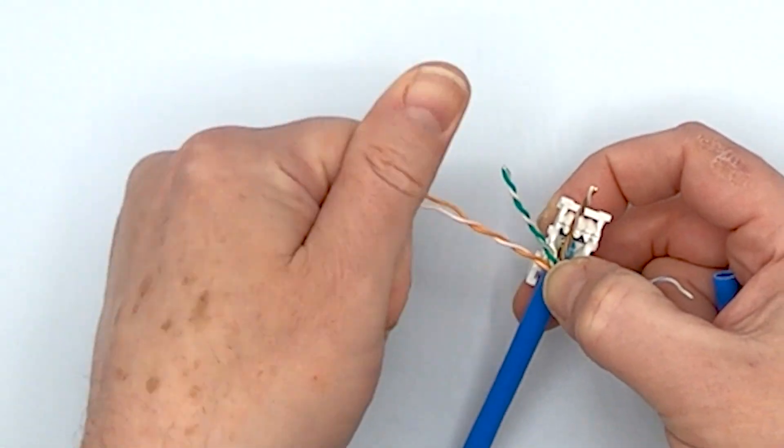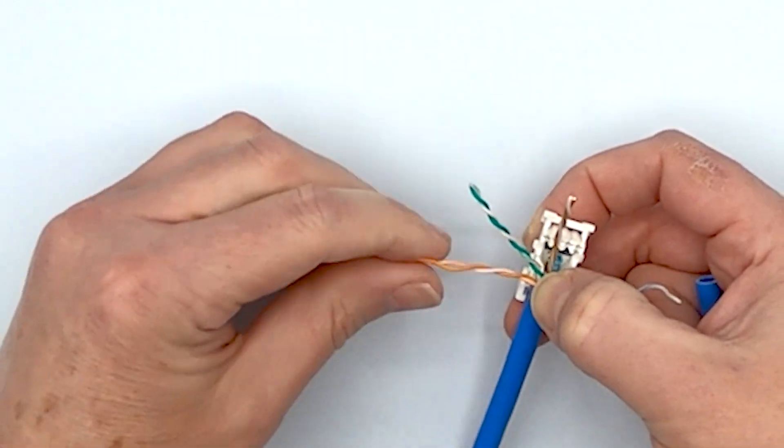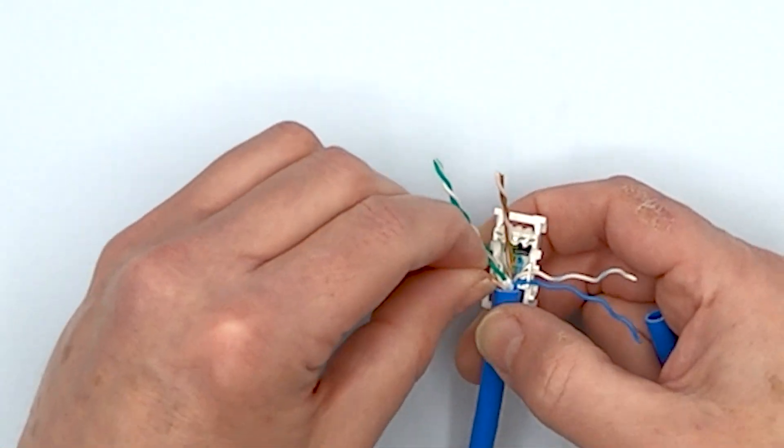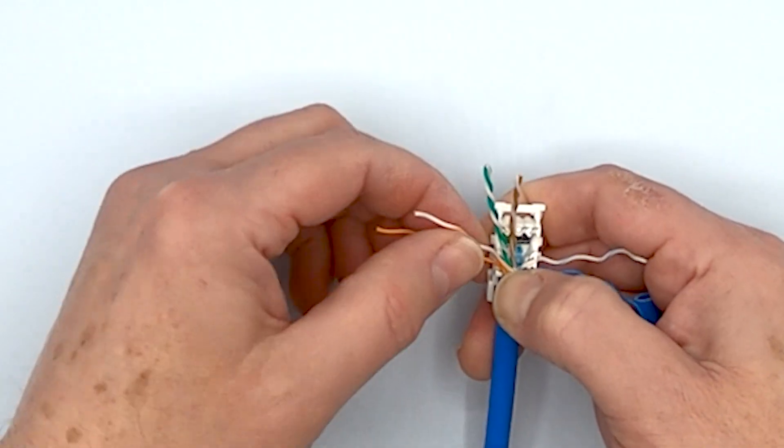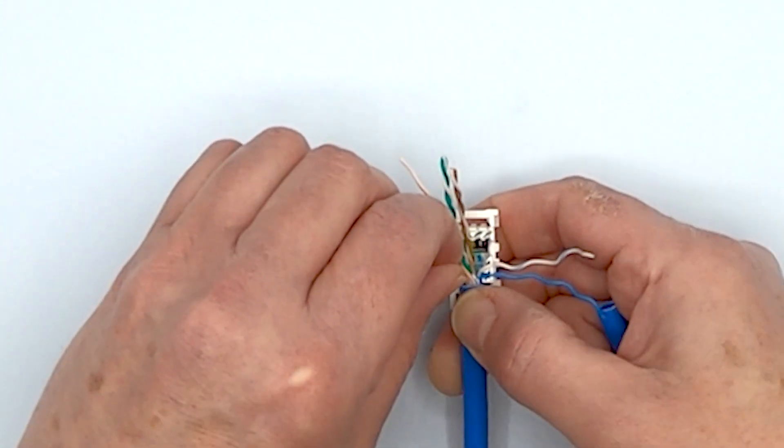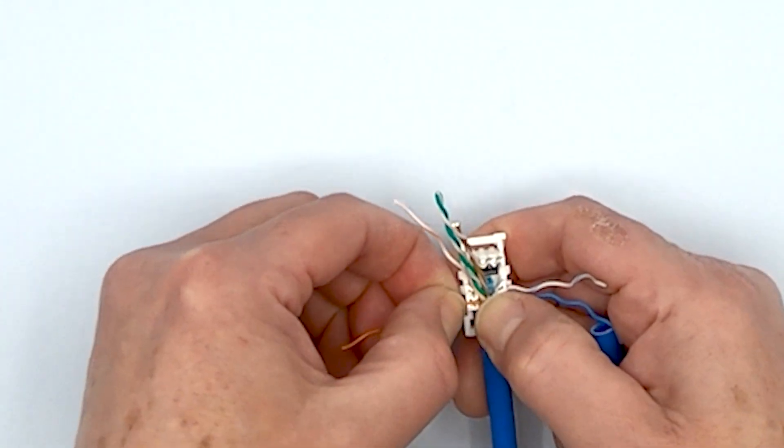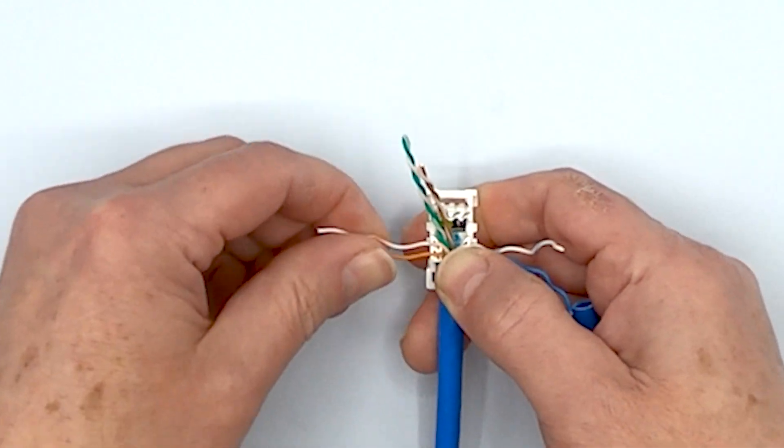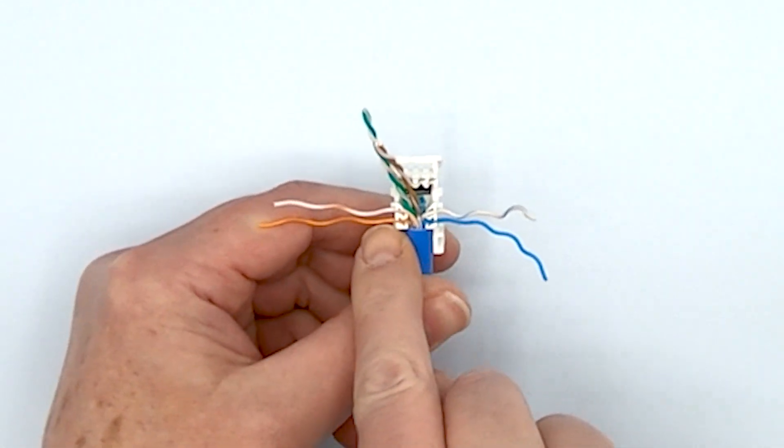Now we'll work with that orange rear pair. You can untwist with your fingers. You can use a piece of cable jacket. The cable jacket's useful because it keeps you from abrading your fingers. We know that the rear is always going to be the solid, so we're going to put that into the rear slot and then the striped orange goes into the front slot.